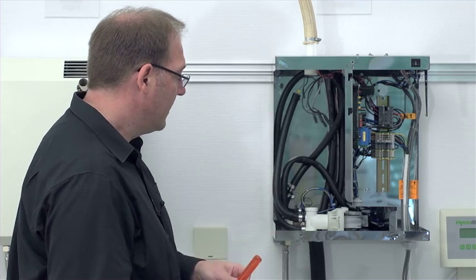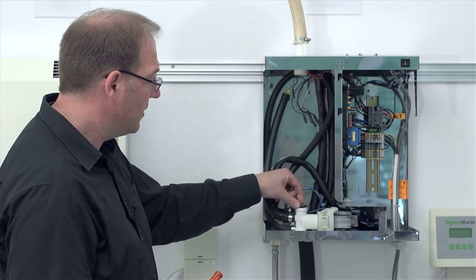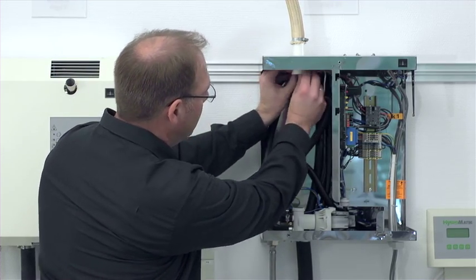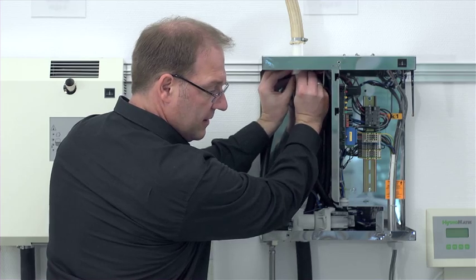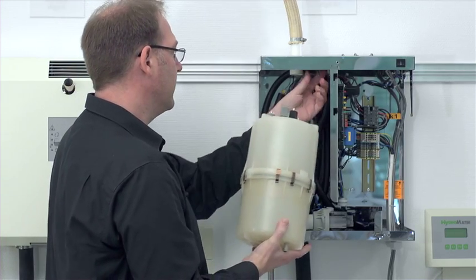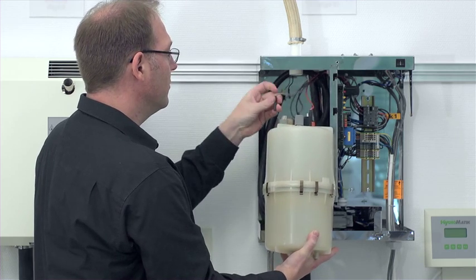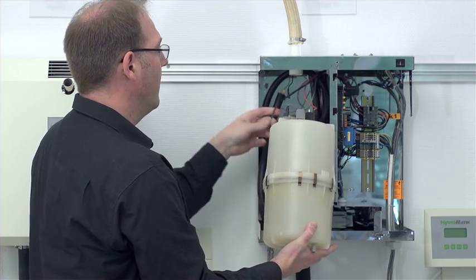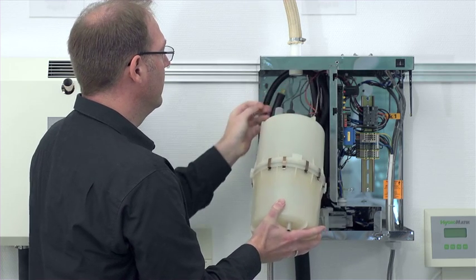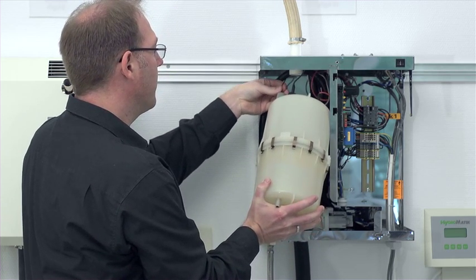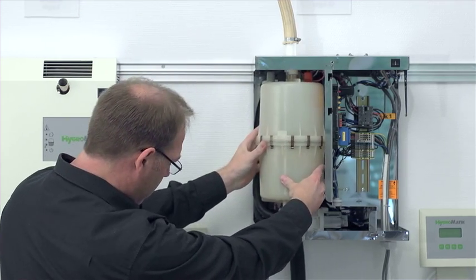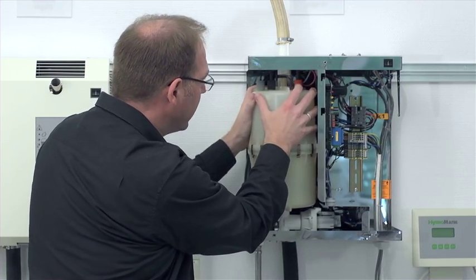I insert new o-rings, one o-ring down in the base and another new one goes up on top in the steam hose adapter. I place it up in the groove and then I can hook the steam cylinder back up to the power supply on top. The electrode connection plugs are attached and then the small sensor electrode, and then I place the cylinder into the base.